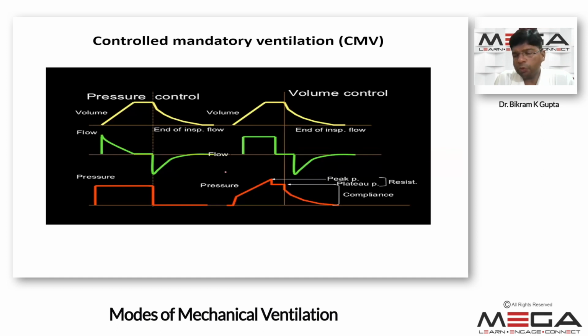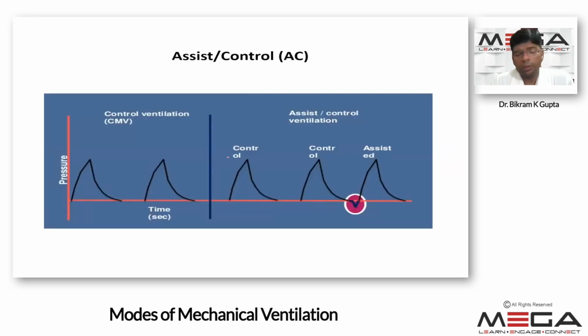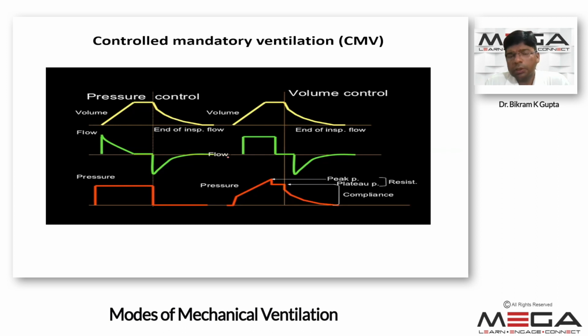pressure. In both modes, we have to fix the inspiratory and expiratory ratio, respiratory rate, and presence or absence of inspiratory pause. But in pressure control, we have to set the pressure limit to achieve the target volume, and in volume control, we have to set the target volume or tidal volume. This mode of ventilation we can use in patients who have a neurological injury, where you want to keep the patient on elective ventilation, or the patient with tetanus, or in the initial period of mechanical ventilation where a lot of patient-ventilator asynchrony was there.